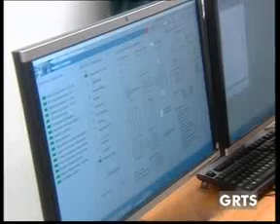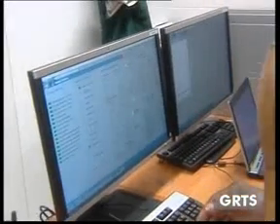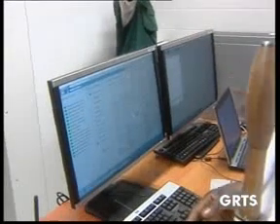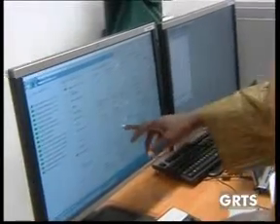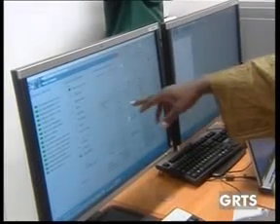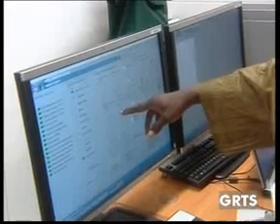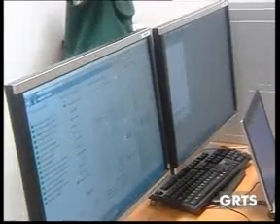So now when the engine is on, you can sit here and see what is going on. You can see all the parameters in terms of the output and all the other parameters like the current, the voltage, and the energy that is being supplied. If it shows red, that means that one of the conditions is not fulfilled. But everything is green, so every condition for an easy start of the engine is fulfilled.